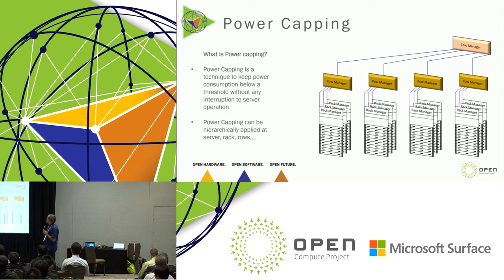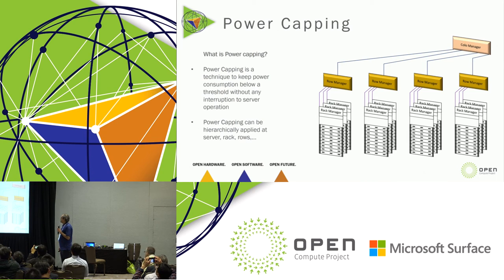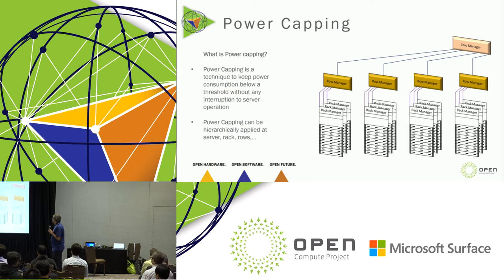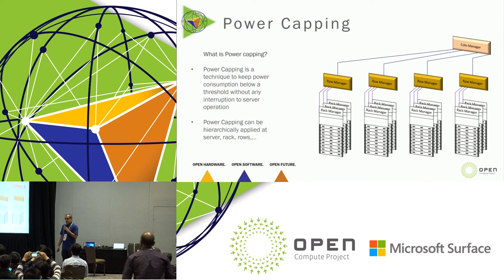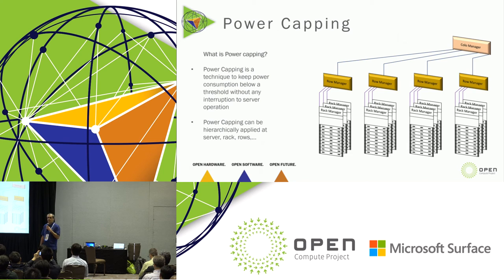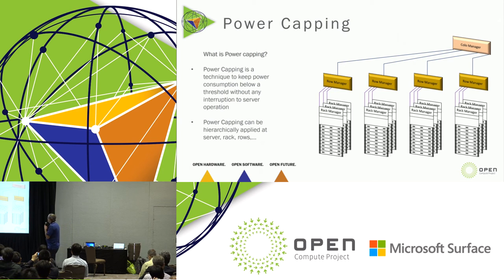So what is power capping? Power capping is a technique — for some of you who may not be familiar with this terminology — it's used to keep power consumption below a threshold without any interruption to server operation. Power capping is implemented in a hierarchical way in the data center. We don't have infinite power and cooling capacity; we have a limit, a power budget defined at the data center.